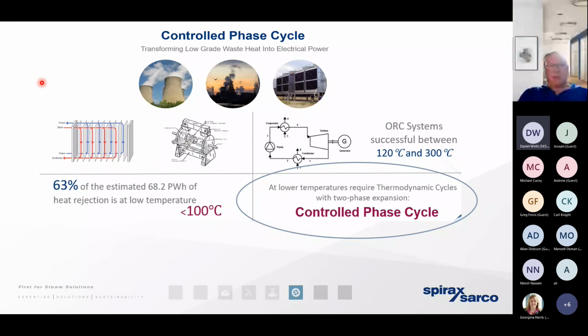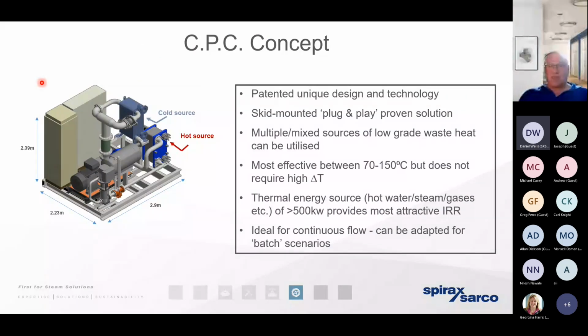And a CPC is a typical skid mounted unit. And essentially, it takes the waste heat energy from the effluent stream, it passes it across a thermal barrier, it causes the gas on the secondary side to expand. That expansion spins a turbine, and that turbine generates a small amount of electrical energy. The key word here really is a small amount of electrical energy.